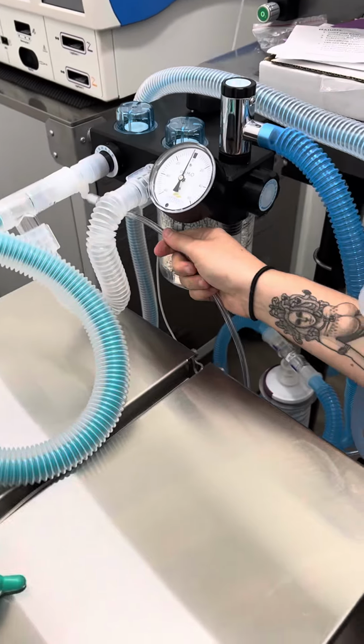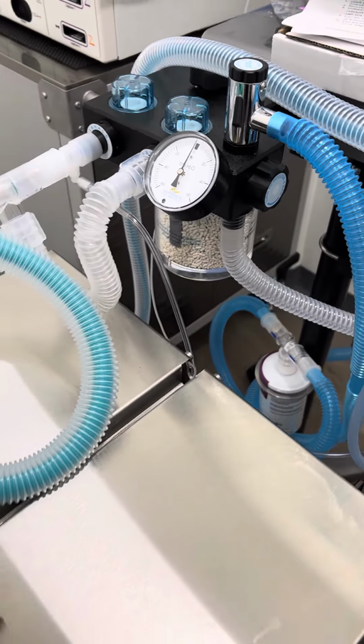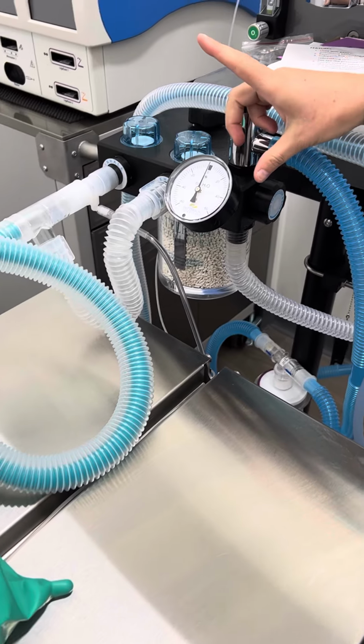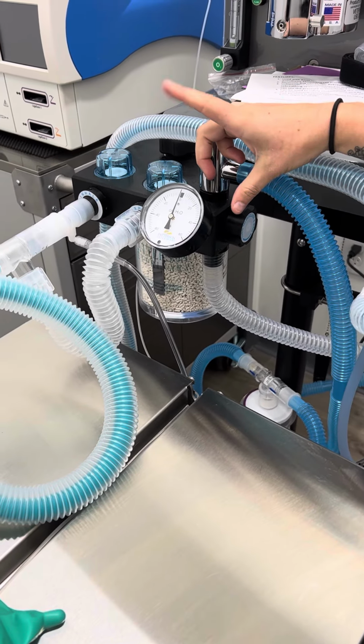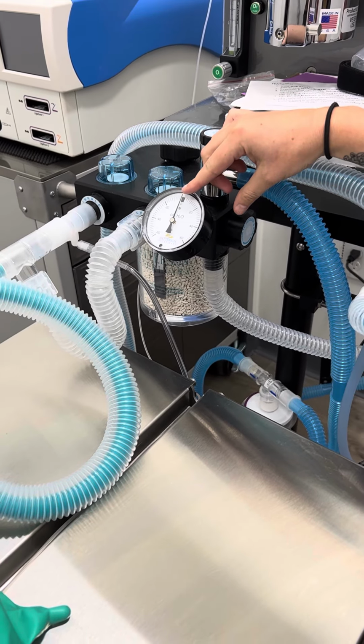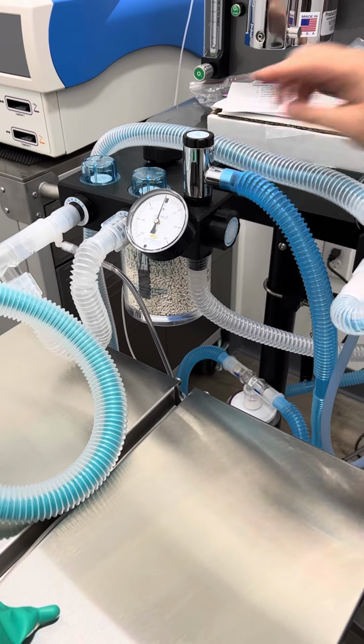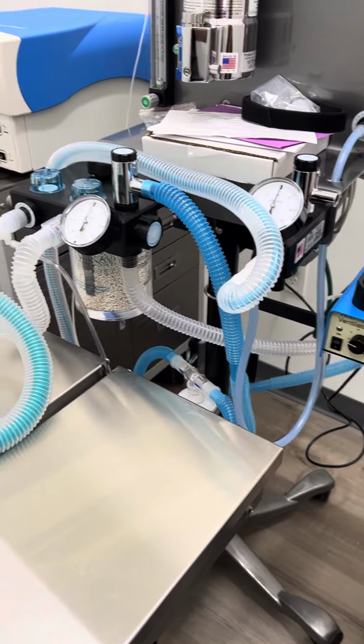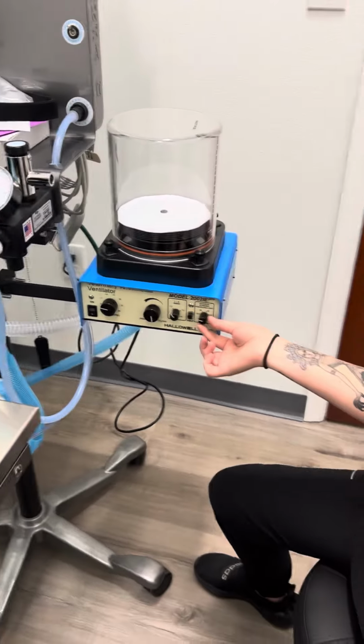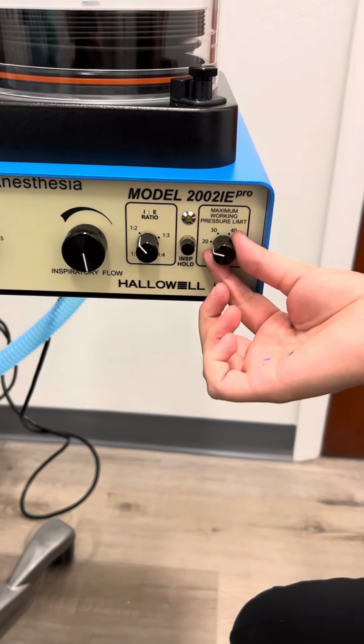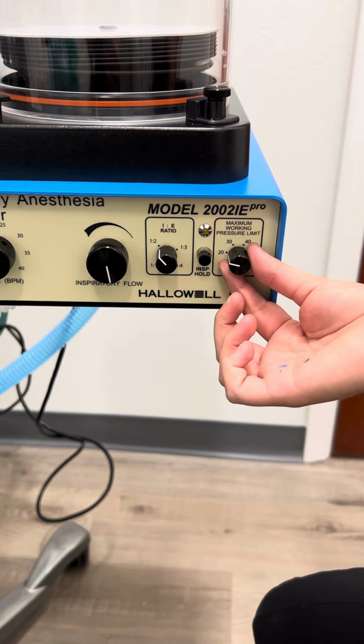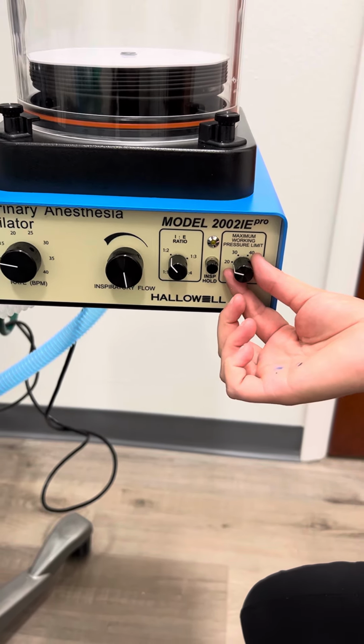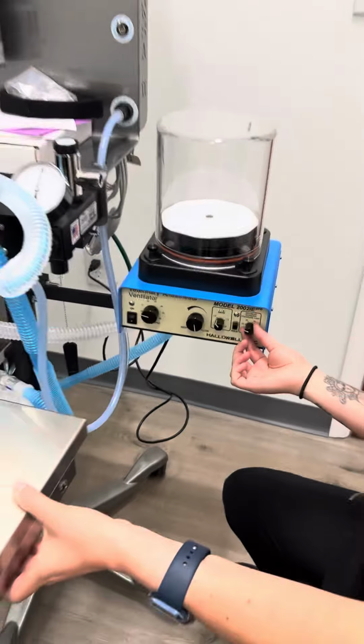This pressure transducer is basically monitoring the centimeters of water whenever the ventilator gives a breath, and it will alarm if the centimeters of water are higher than whatever you set the maximum working pressure limit to. So I'm going to turn it on and give an example of what that alarm looks like.